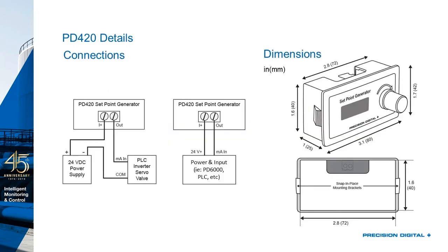Here's a couple simple diagrams that show you how this connects to things. So here we have our 4 to 20 set point generator. In this case, we're using a 4 to 20 milliamp input device like a PLC, inverter, servo, or valve positioner, and a separate 24-volt power supply. So we're coming out of our 24-volt power supply, going into our loop-powered set point generator. You're going to use that dial on the front to set whatever you want the 4 to 20 milliamps to be. And it's going to come out of that and into your PLC, valve positioner, etc. Then you just connect the common on that input device back to the power supply, and you've got your 4 to 20 milliamp loop.